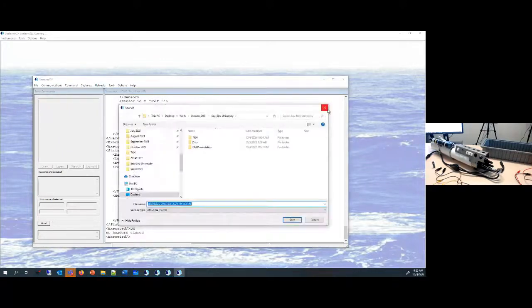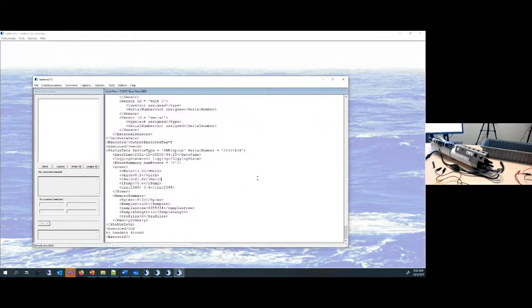What we're warning here is because this is like a VHS tape, if you were to tape over the samples, say you reset logging back to sample 0, you log some data and then stop logging data, it's going to record over those previous samples that you had in the memory and prevent you from recovering data like this. So this is a trick you can use, especially if you have a ton of samples in memory, to hopefully recover some of your data. But it's not foolproof. It's not to say that these samples are always in the memory. If you overwrote them, they're gone forever. So be careful when you initialize logging, and always make sure to upload your data as much as possible.